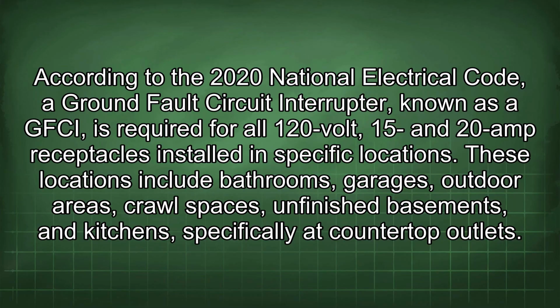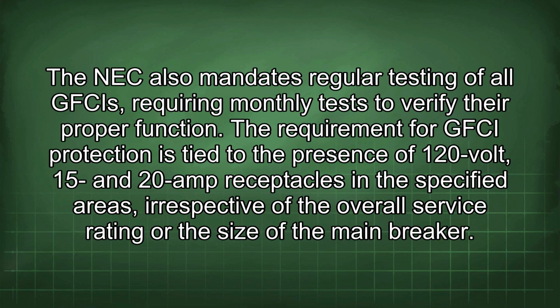According to the 2020 National Electrical Code, a ground fault circuit interrupter, known as a GFCI, is required for all 120-volt, 15 and 20 amp receptacles installed in specific locations. These locations include bathrooms, garages, outdoor areas, crawl spaces, unfinished basements, and kitchens, specifically at countertop outlets. The NEC also mandates regular testing of all GFCIs, requiring monthly tests to verify their proper function.